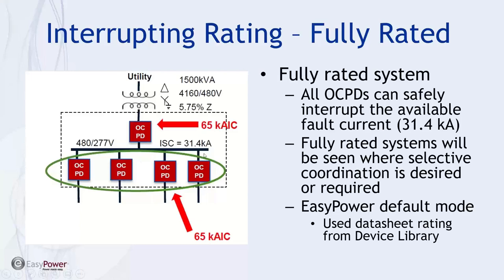Not to confuse coordination with series rating — it is basically important that all the equipment in your one-line can withstand the worst-case fault at any particular bus. From a manufacturer's data sheet, a device has a rating and its capability to operate within a range of fault current. In an application where all devices are rated for 65,000 amps and the worst-case current on a bus is 31,400 amps, all are compliant — a fully rated situation.